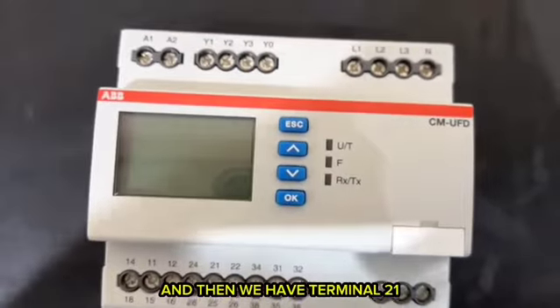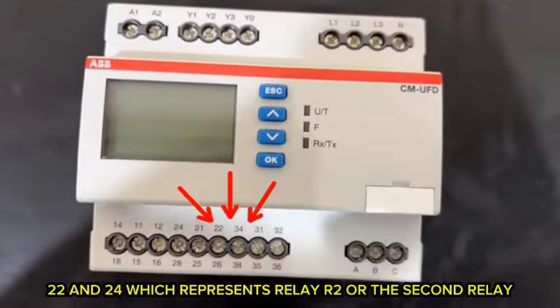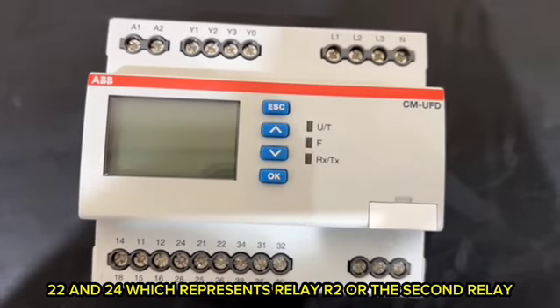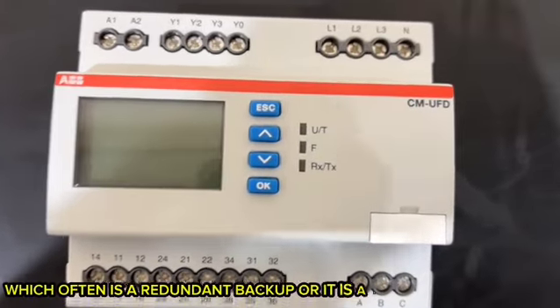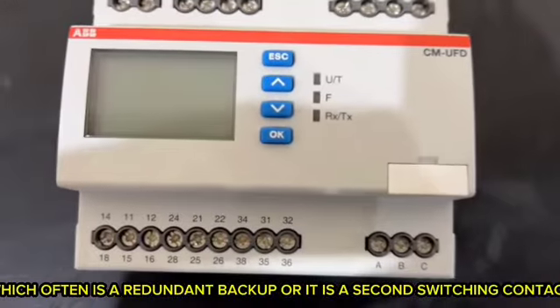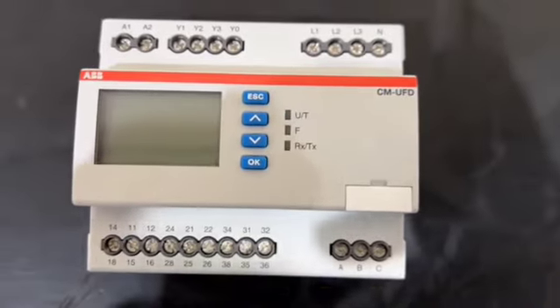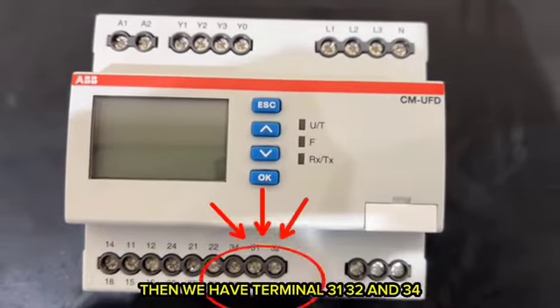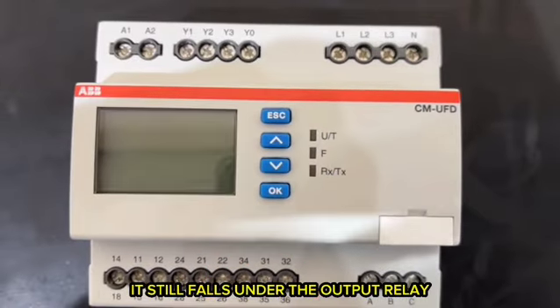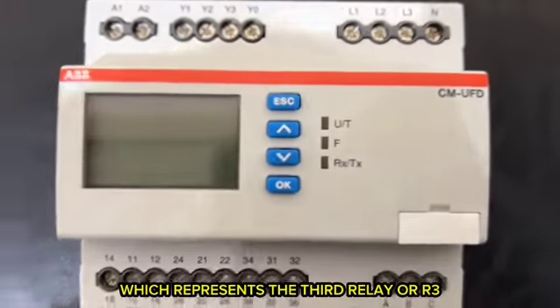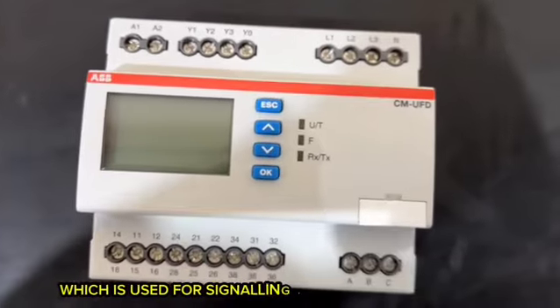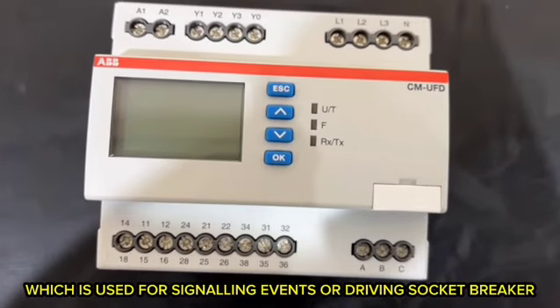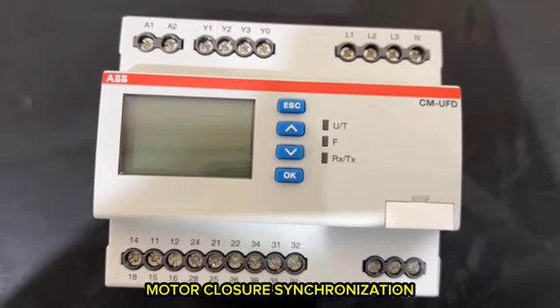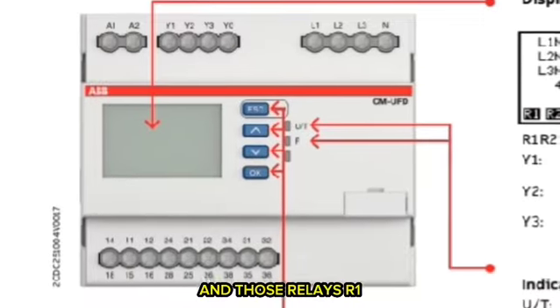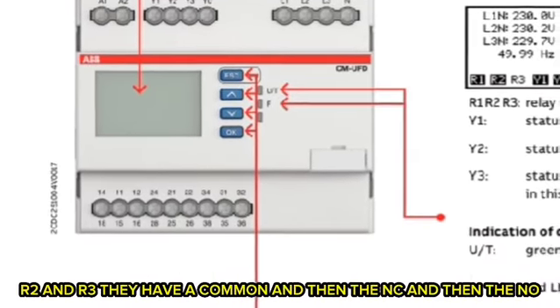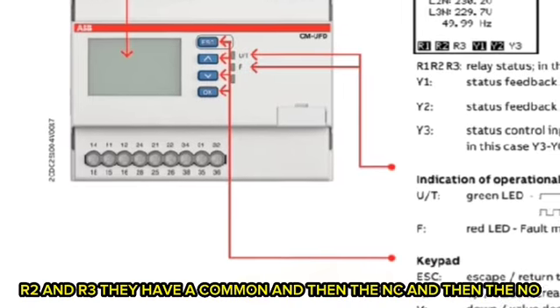And then we have terminals 21, 22 and 24, which represent relay R2, the second relay, which often is a redundant backup or a second switching contact. Then we have terminals 31, 32 and 34. It still falls under the output relays, and represents the third relay, R3, which is used for signaling events or driving circuit breaker motor closure synchronization. Those relays, R1, R2 and R3, have a common, and then the NC and the NO.